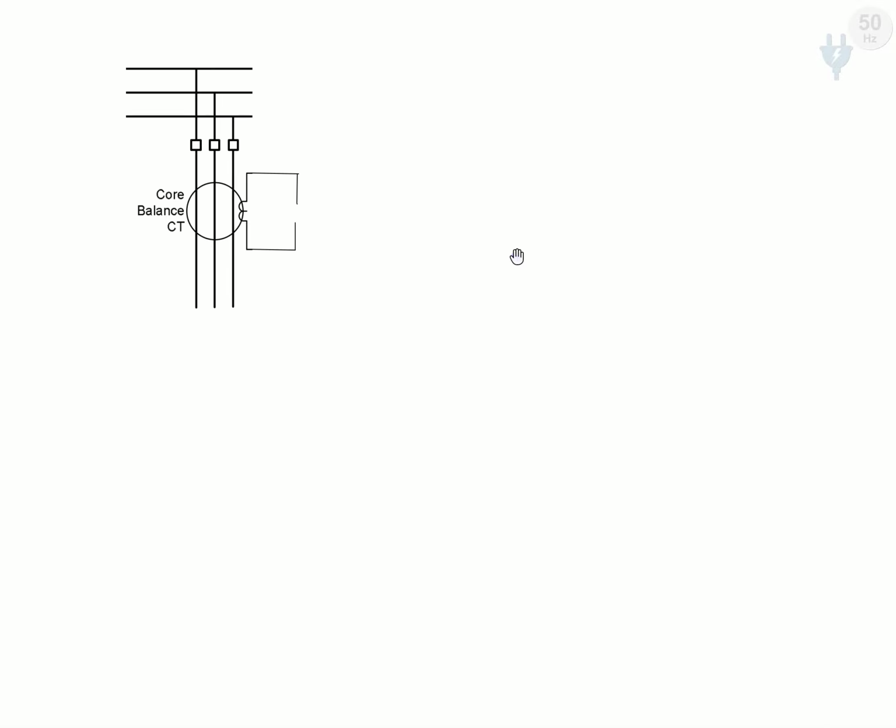Here you can see that if we have a system which is a type of arc suppression coil system grounded or Peterson coil grounded system, then our core balance transformer is installed, and we expect that, for example, at the amount of the current which is flowing in the line and during the fault, what amount of the current will be in our secondary of the core balance transformer.